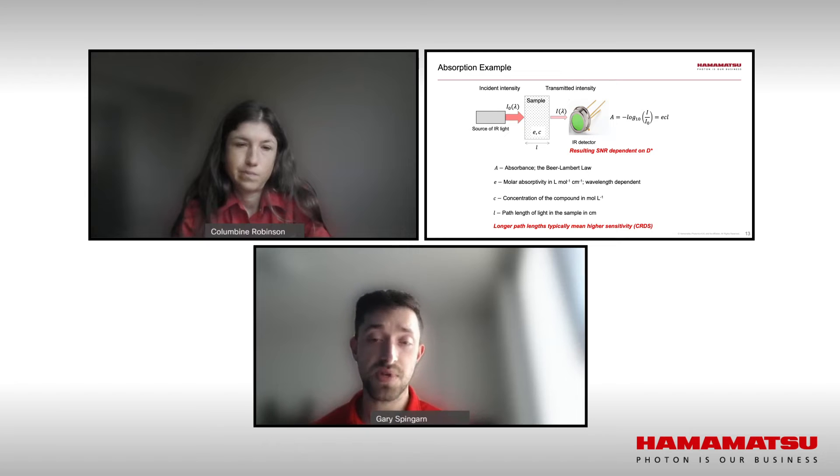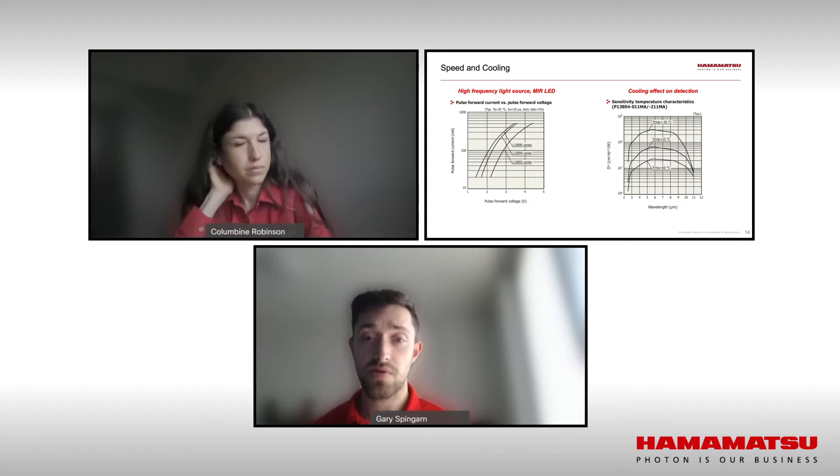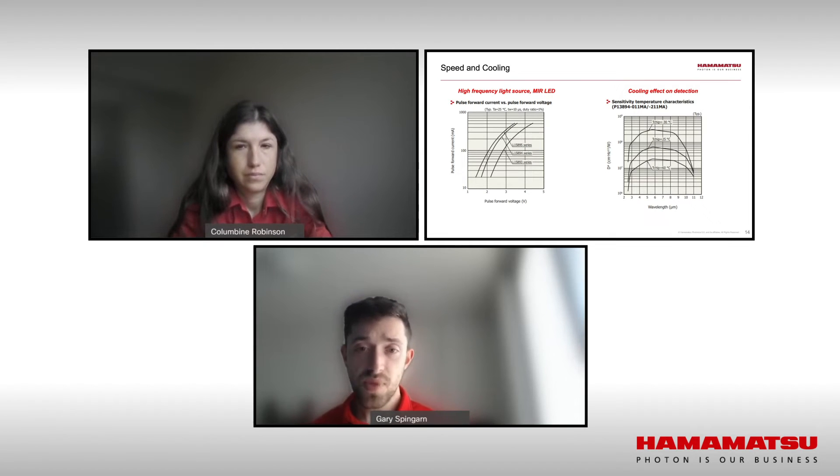Next comes speed. Some detectors simply are going to have a signal drop-off at higher frequencies. The problem here is that some IR light sources are going to operate at high frequency modulation. So if one is using one of these light sources, one needs to choose a detector that can keep pace.